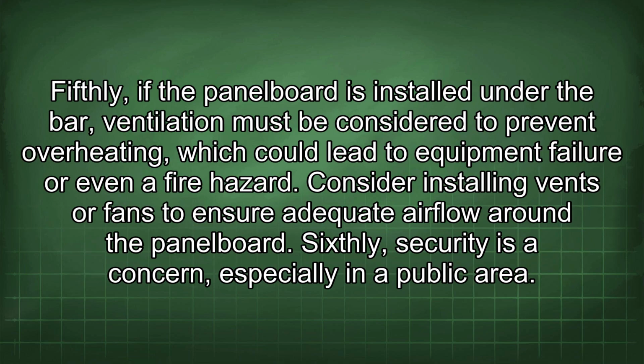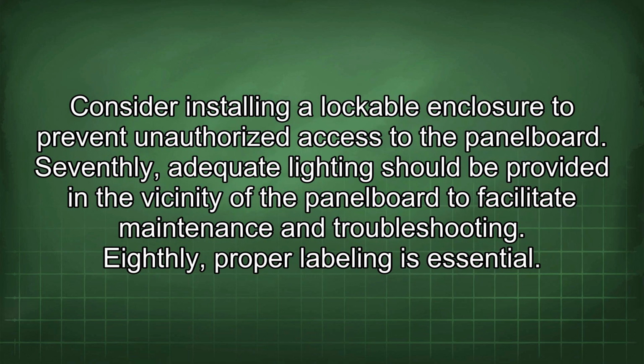Fifthly, if the panelboard is installed under the bar, ventilation must be considered to prevent overheating, which could lead to equipment failure or even a fire hazard. Consider installing vents or fans to ensure adequate airflow around the panelboard. Sixthly, security is a concern, especially in a public area. Consider installing a lockable enclosure to prevent unauthorized access to the panelboard. Seventhly, adequate lighting should be provided in the vicinity of the panelboard to facilitate maintenance and troubleshooting.